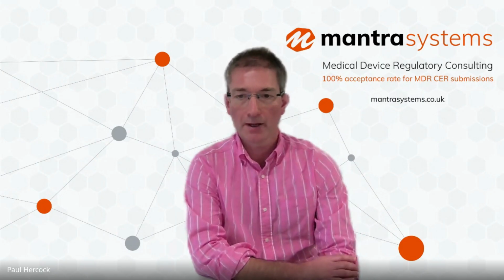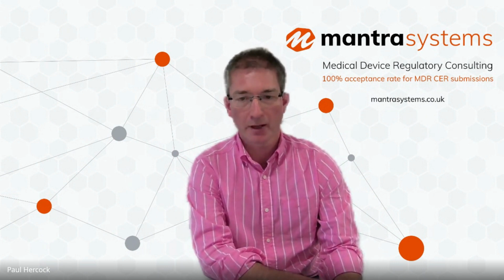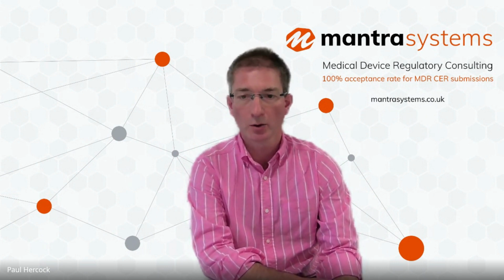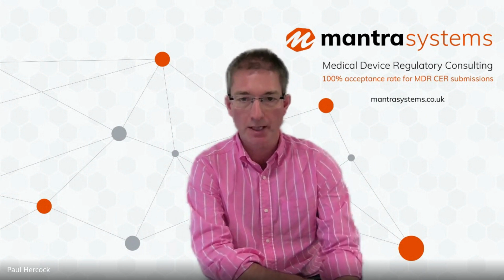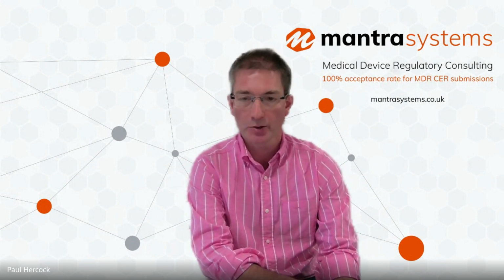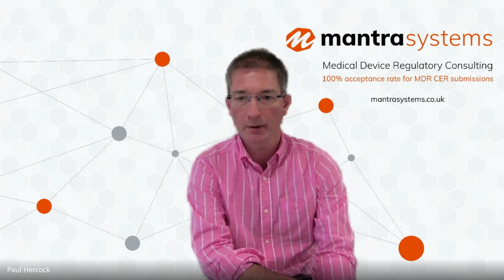And this is, do I need a CER even if my devices are all class 1? Yeah, this is a common inquiry that we get, to be honest. The answer is yes, you do. All devices of all types need a clinical evaluation, and that's under both the UK MDR and the EU MDR.